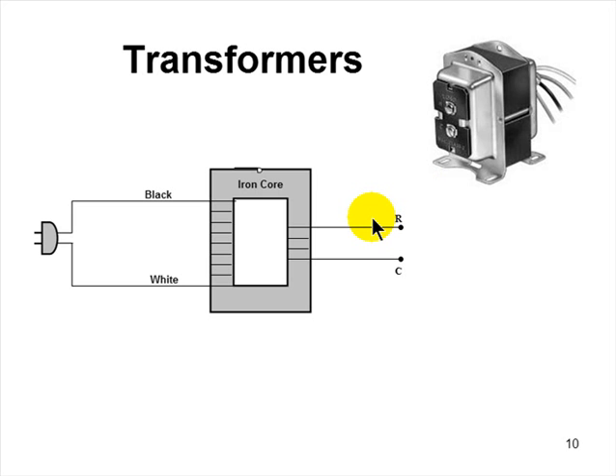So, this brings us to transformers. Why are we talking about transformers? Because a transformer is a big old magnet. When you look at a transformer, basically it's built like this. This side gets plugged into the wall. And what you do is you wrap, and I'm showing it wrapped right around this iron core that I made very conveniently here. It's a wrap like a winding on a motor, in proximity to that iron core, because the iron core is going to intensify the magnetic field that's set up here. So this is the one winding. The other winding, in this case, since it's a step-down transformer, has fewer turns in it. But it's not connected physically to anything. This wire is all insulated. There's no continuity between this point and that point.